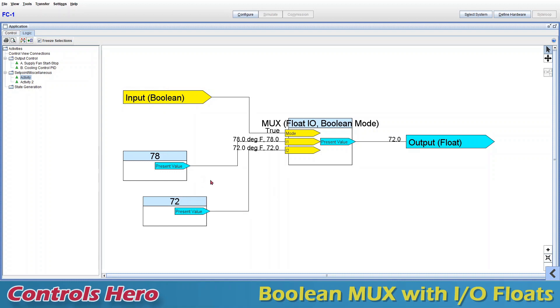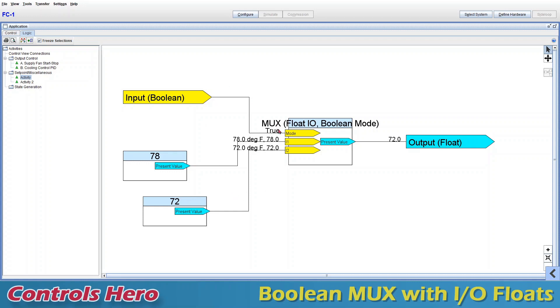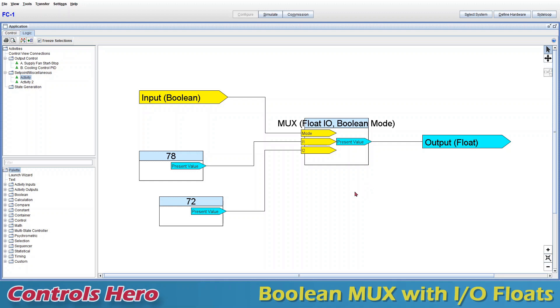I picked these two numbers to show you an application for this multiplexer. Let's say that when our system is occupied we want to have 72 as the room temperature set point, and when the system is unoccupied we want the set point to be 78. We can solve that with a boolean multiplexer — if it's unoccupied (false), it outputs 78, and if it's occupied (true) we pick 72 as the new set point.